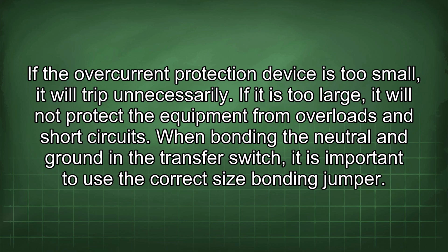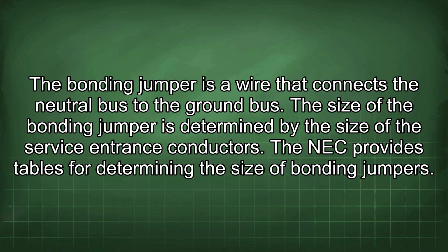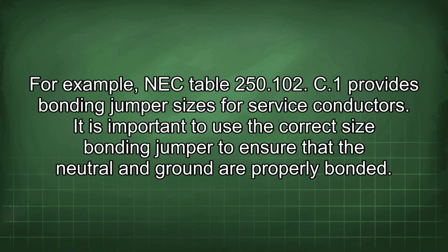When bonding the neutral and ground in the transfer switch, it is important to use the correct size bonding jumper. The bonding jumper is a wire that connects the neutral bus to the ground bus. The size of the bonding jumper is determined by the size of the service entrance conductors. The NEC provides tables for determining the size of bonding jumpers.